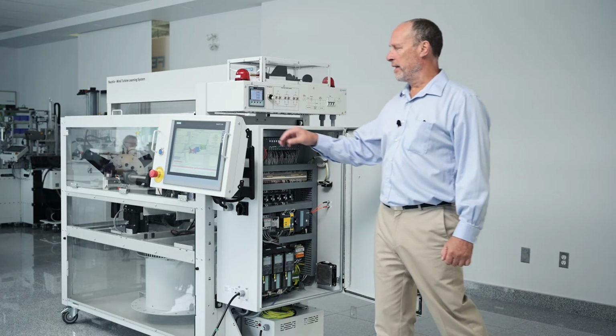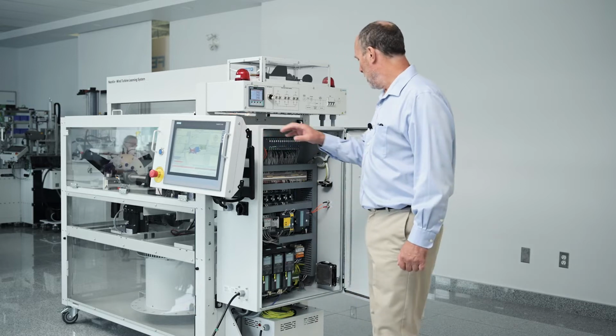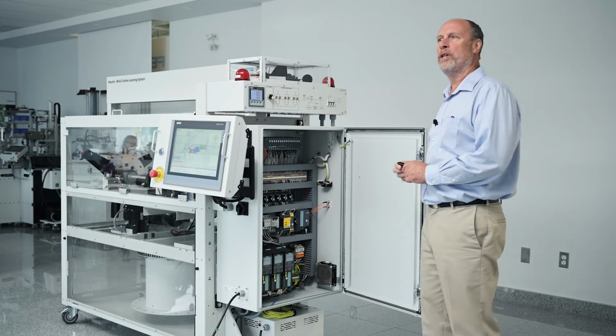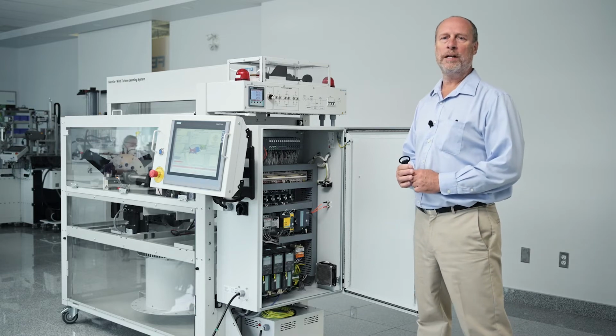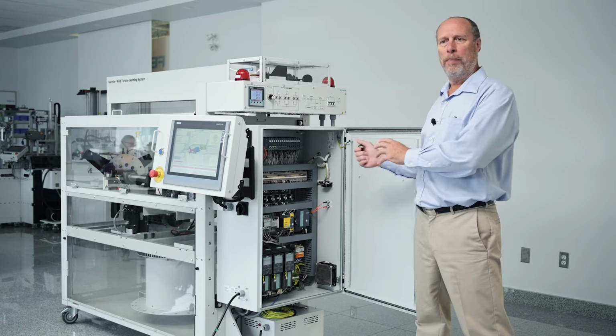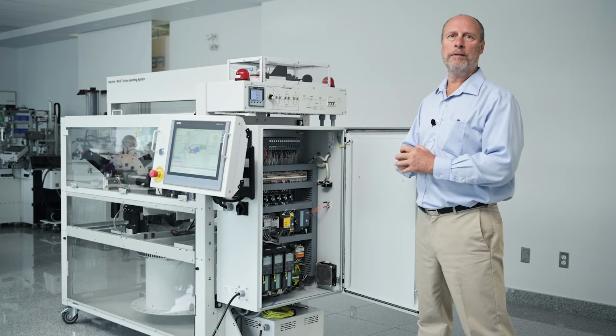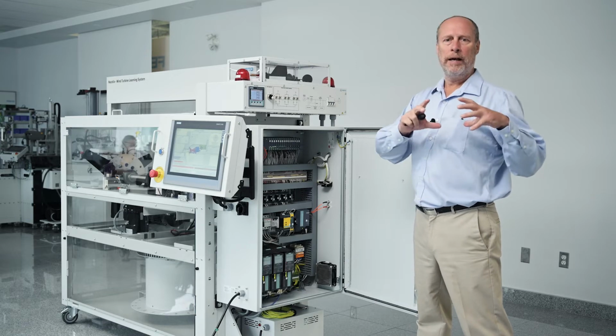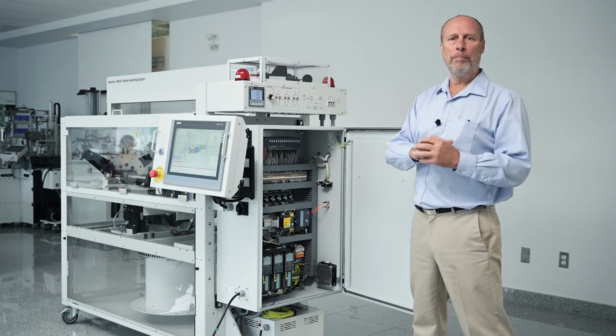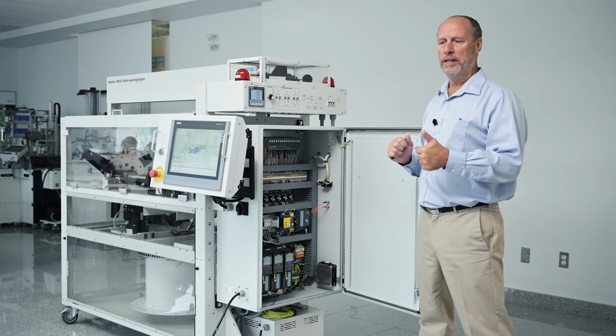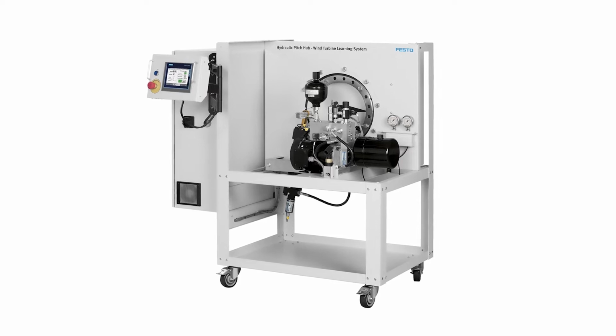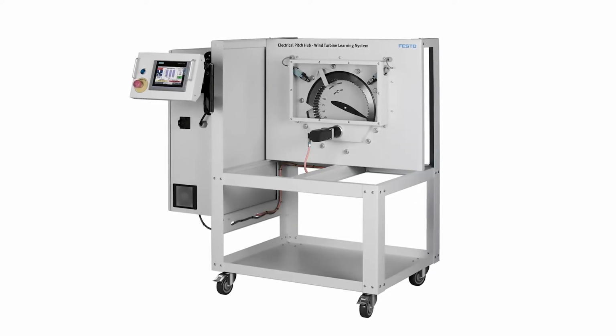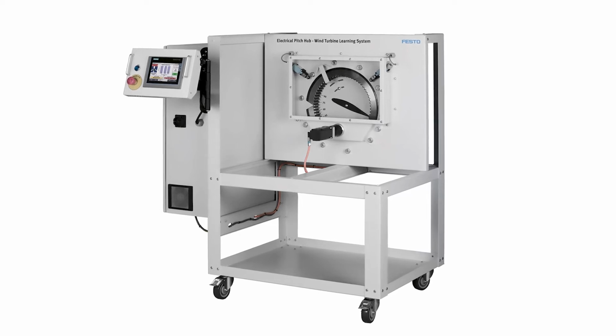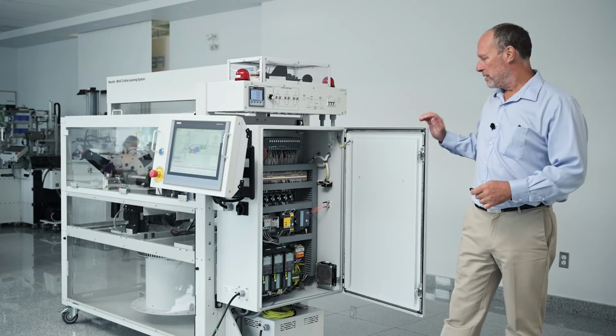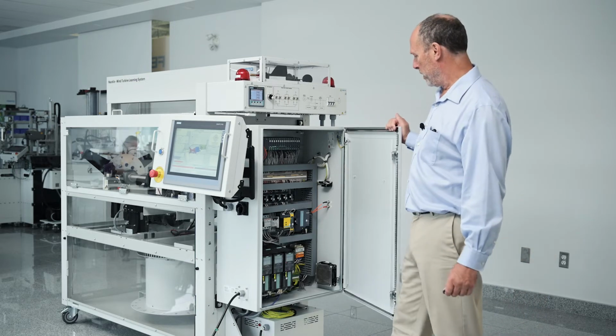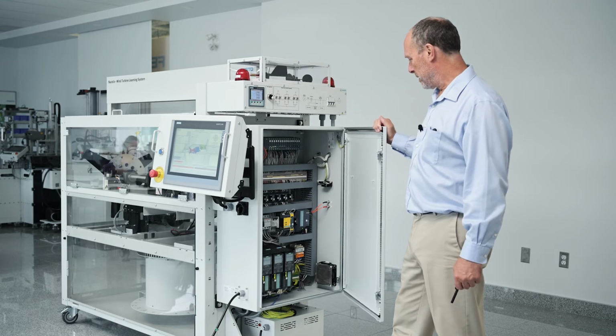And the PLC is linked to this HMI. Also, provision is taken to network the pitch hubs that we have. So the nacelle is one part of the system. If you want a complete wind turbine system, then we have another unit, which is the variable pitch controllers. So we have one trainer which is the hydraulic pitch hub, and we have also the electric control of the pitch. So these are readily made to be synchronized in a network manner with the nacelle. So that's it.